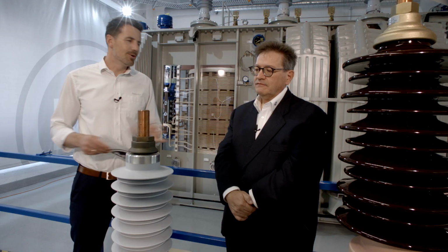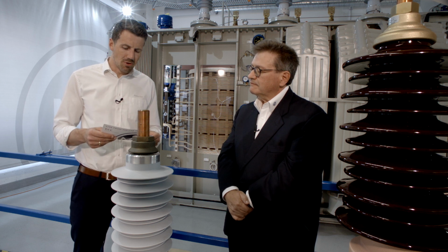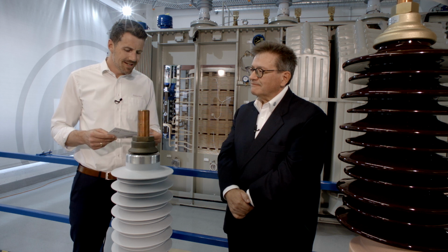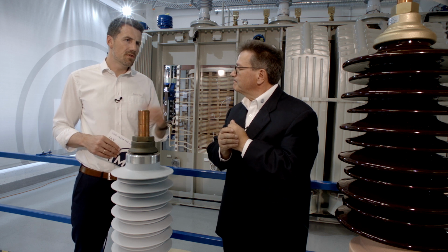Thank you, Stefan. So, Tullio, when talking about bushings, we firstly need to talk about application ranges. What are typical application ranges CEDASPE is specially manufacturing nowadays? CEDASPE is manufacturing porcelain bushings up to maximum 52 kV rated voltage and 12.5 kiloamps rated current. We are also manufacturing what we call polymeric bushings up to 52 kV rated voltage and 4,500 ampere rated current. Typical application of this bushing is in the secondary side of small and medium power transformers. Okay. Small and medium power transformers up to 52 kV, you said.